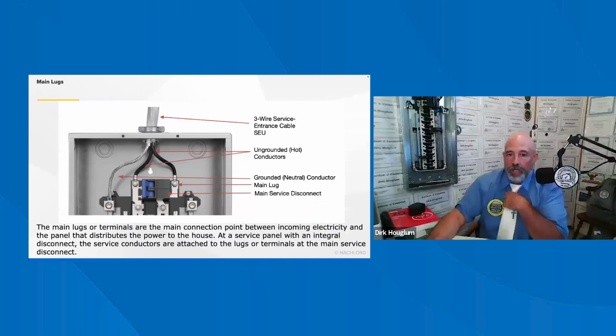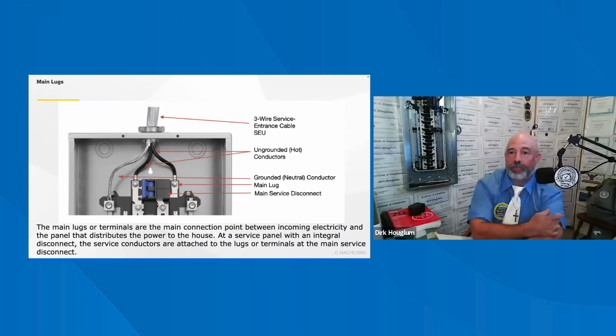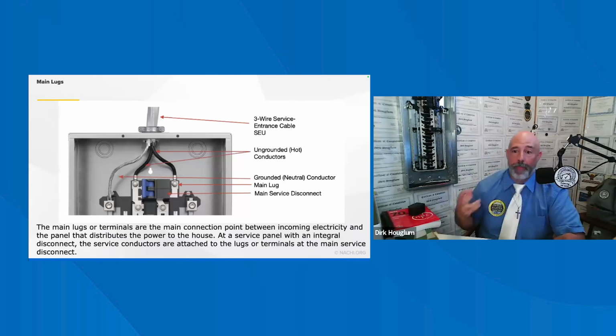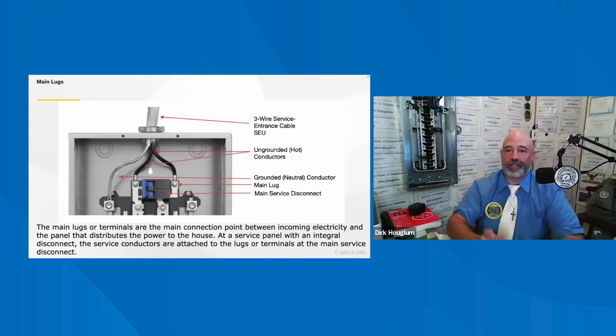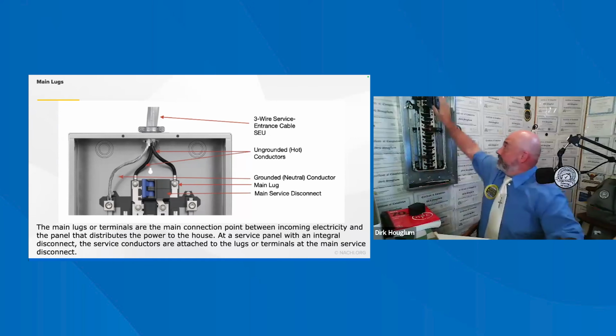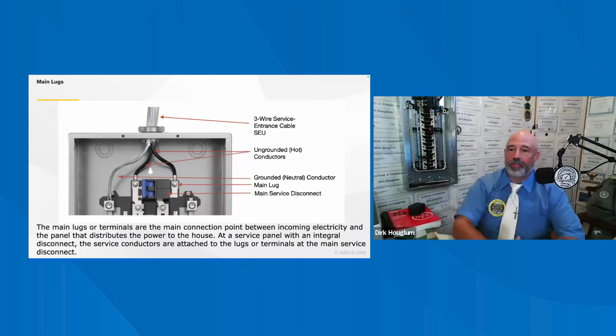Okay. The main lugs, or the terminals, are where the incoming power connects to the panel and gets distributed through the home. In most setups, the main service disconnect, the big main breaker, is built into the panel and serves as the first level of overcurrent protection. Each hot wire connects to the main bus and so on and so forth, and usually it's a large 240 volt switch at the top, like this one here. The neutral wires then connect to the bus bar and so on and so forth.